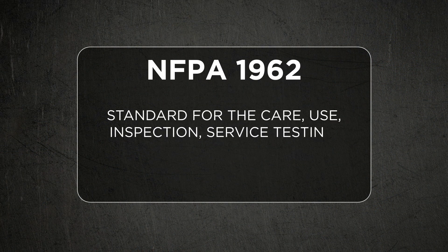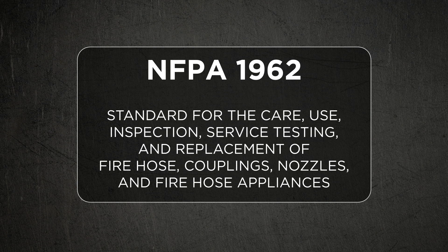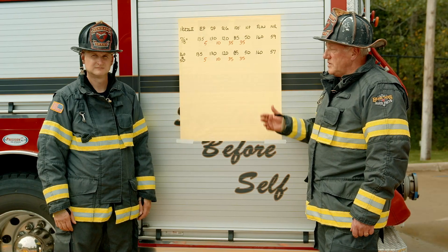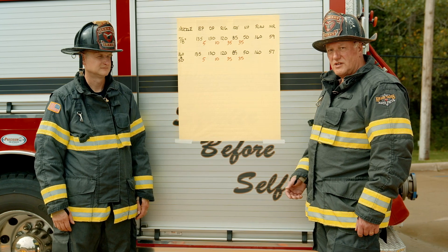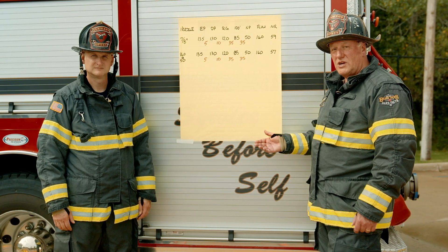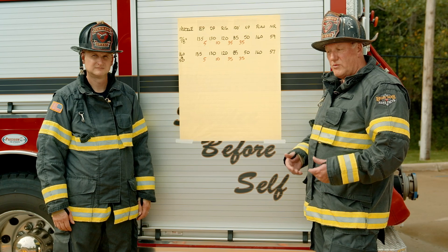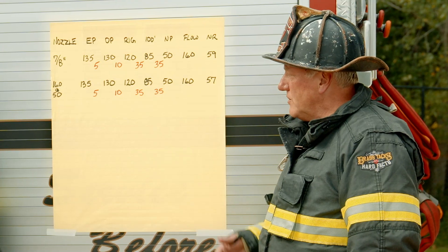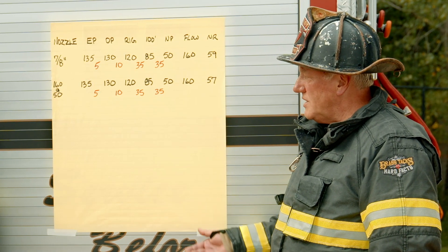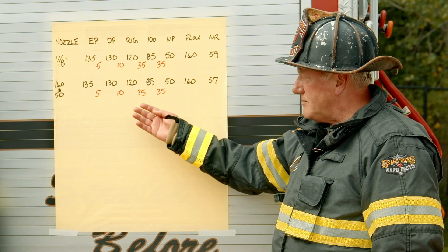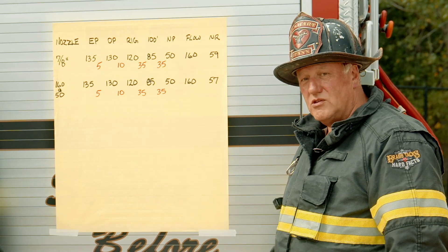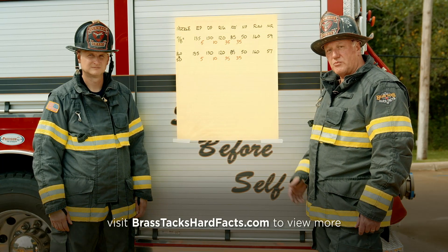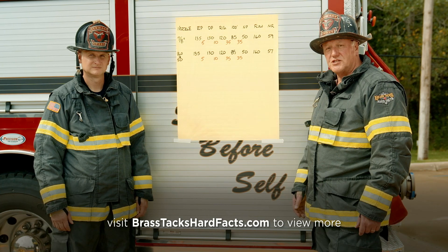The NFPA 1962 standard gives us a simple template approach that can accomplish many objectives. If we were looking to do a complete NFPA 1962 test of the rig, we would gather this information for every discharge. If utilizing this approach for a hose and nozzle evaluation, it would bring it down to an obvious recommendation. If using it to validate discharge flow on every discharge, we'd capture our plumbing loss and identify that we're not flowing what we may think we're flowing. Utilize the standard based on what your objectives are, and it will bring you to the information you need to make a decision.